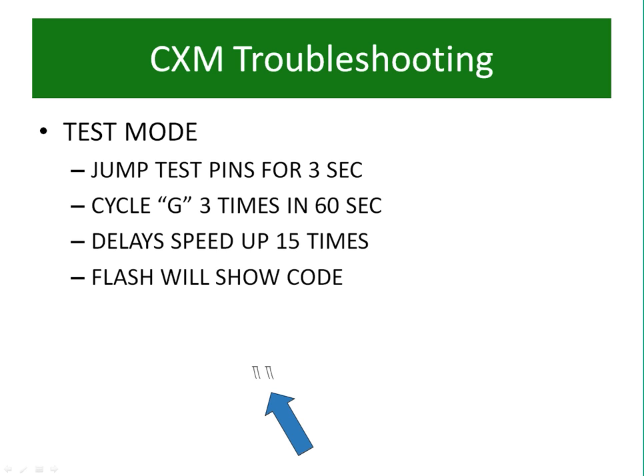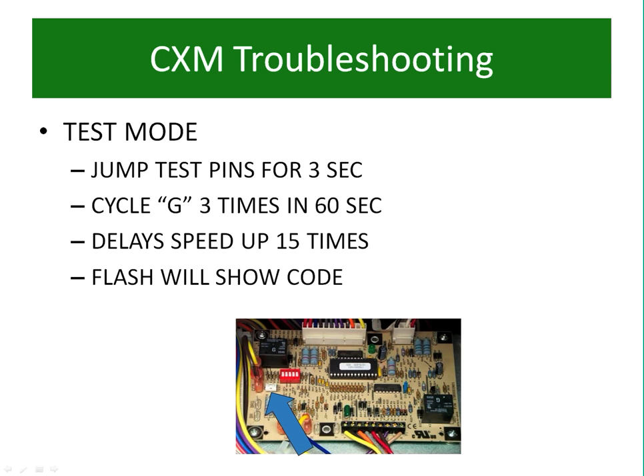The other thing this does is that it speeds up our time delays by 15 times, so you can hurry up and get back onto that compressor cycle. Remember, we have about a 15% bleed by on our TXV, so it doesn't take but a couple minutes for you to get equalization on your refrigerant pressures.